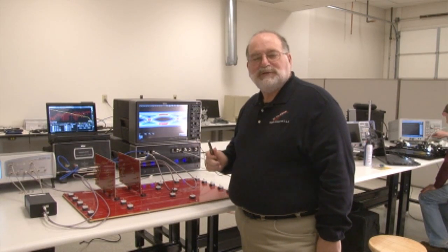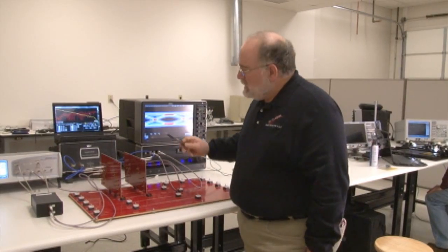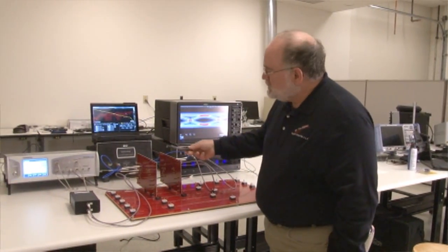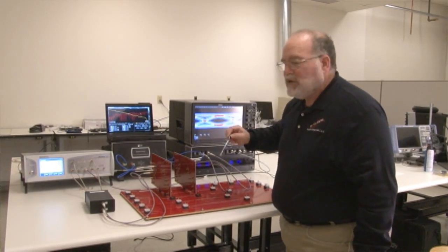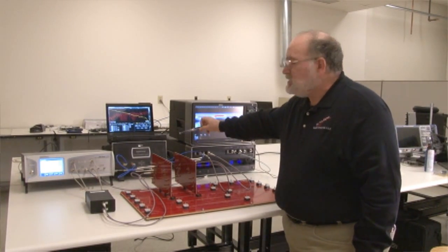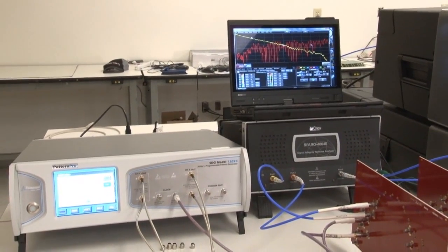In this first measurement, we're going to look at the S parameters for a backplane channel. Here's the backplane channel that we're going to measure. It's about 16 inches long from the SMA connectors on the end to the other end.